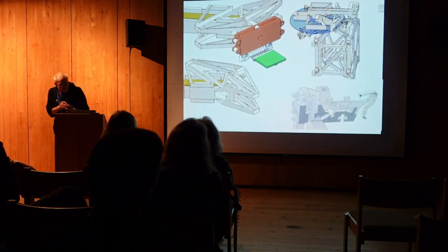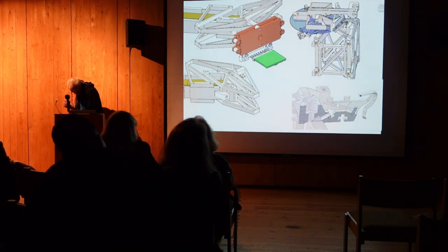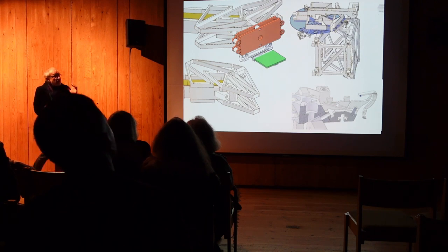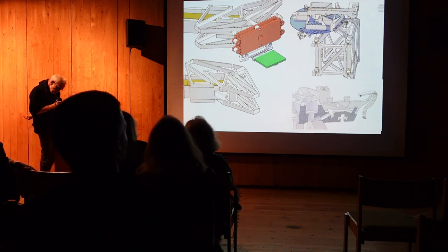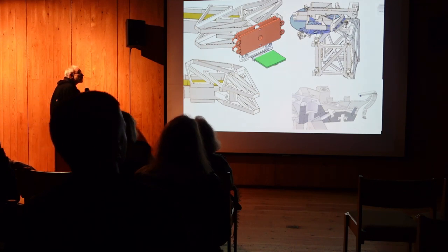The one thing that we have been trying to get to run, which we think is important, is that it's difficult to move the sample fast enough between image acquisitions. So we built a piezo stage, it's actually running now, that does this move quickly, within something like 50, 100 milliseconds, without making the whole microscope rattle with resonances. And since the slices are on a wafer, they have to move back and forth to get imaged and then milled. There has to be a transfer mechanism, and it has to be reliable.